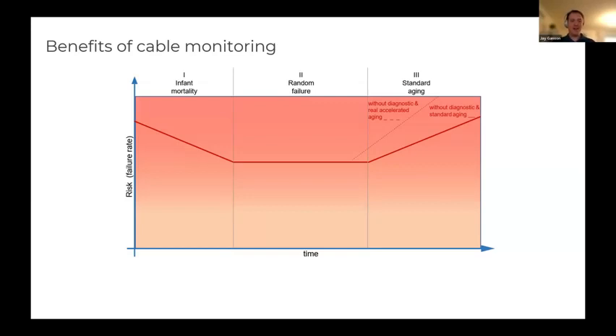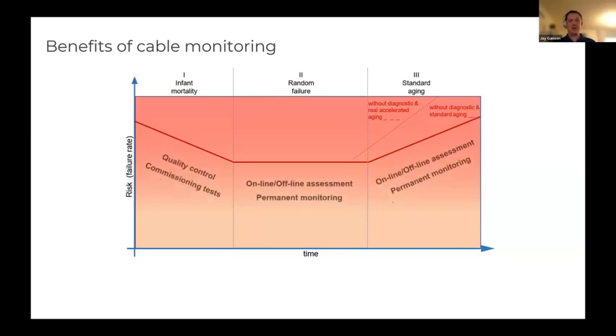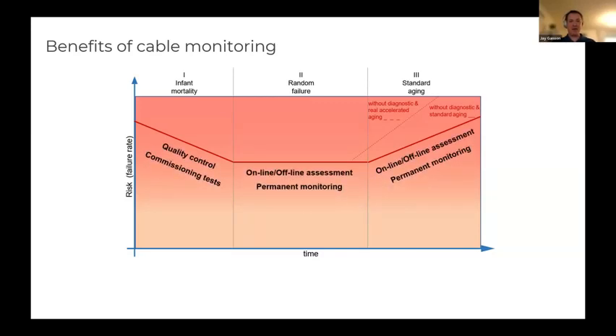And if we think of, Tony and I have had some discussions about this curve and if it really is applicable to certain cable assets. But with many electrical assets, we think of a common risk curve of when we put an asset in service with infant mortality, the life of the asset having random failures, and then some sort of increased failure with aging. A lot of what we do with condition monitoring, specifically on cables, is to bring that risk down. And we can do that on all levels or all stages of a cable's life.